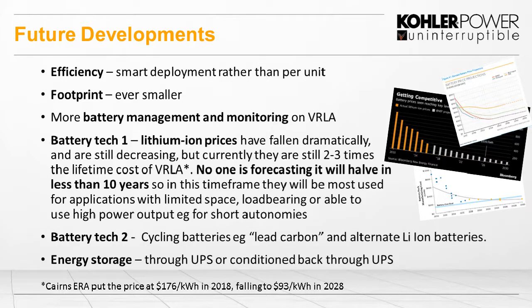But we see a lot of cyclic use now on batteries, not so much on UPS, but there's a lot of talk about it. And we see alternatives to lithium with different types of lead batteries with different chemistries, such as lead carbon. And again, another trend going forward is energy storage systems. Now there's an ongoing look at, do we use UPSs for supplying some of that energy storage? Do we use the UPS to condition it back through, or do we use completely separate systems? But with the grid being dependent on energy storage, I think the UPS is going to be extremely critical in keeping it smooth. So that actually brings us to the end of the presentation today.